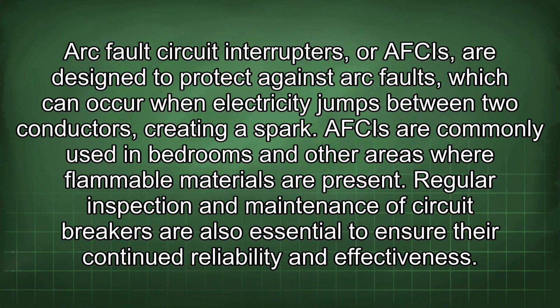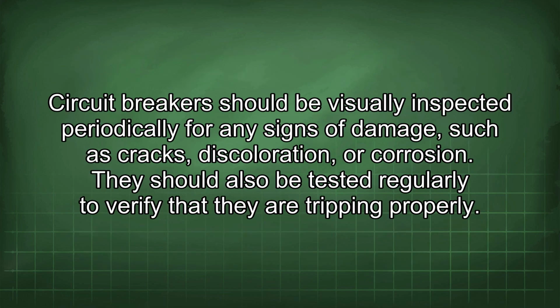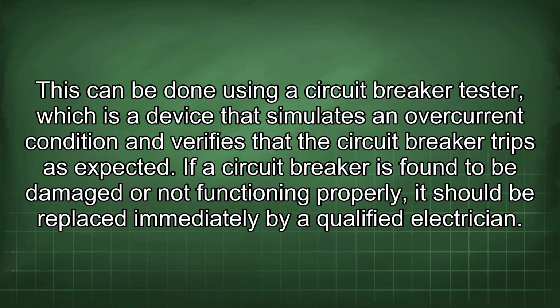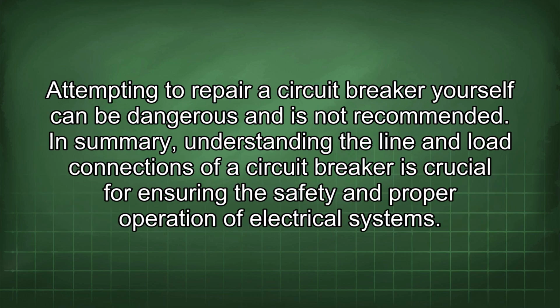Regular inspection and maintenance of circuit breakers are also essential to ensure their continued reliability and effectiveness. Circuit breakers should be visually inspected periodically for any signs of damage, such as cracks, discoloration, or corrosion. They should also be tested regularly to verify that they are tripping properly. This can be done using a circuit breaker tester, which is a device that simulates an overcurrent condition and verifies that the circuit breaker trips as expected. If a circuit breaker is found to be damaged or not functioning properly, it should be replaced immediately by a qualified electrician. Attempting to repair a circuit breaker yourself can be dangerous and is not recommended.